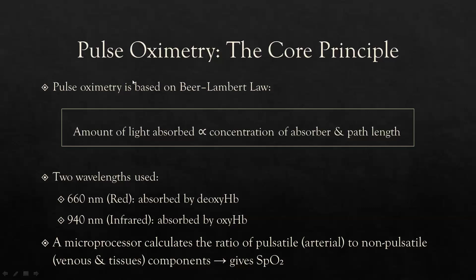Beer-Lambert's law. This indicates how pulse oximeters work due to hemoglobin's ability to absorb light. Basically, any liquid has the property to absorb light to some extent based on the concentration of the liquid and the type of the liquid. Rest of the light is transmitted on the other side, which is received by the receiver. Based on the difference between these two, we get the reading on the pulse oximeter.